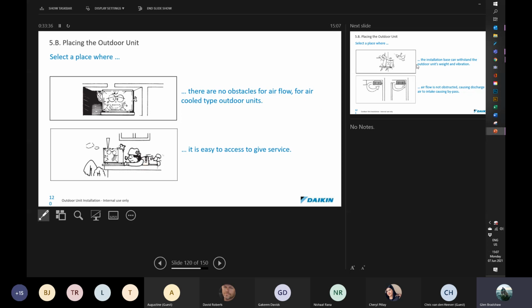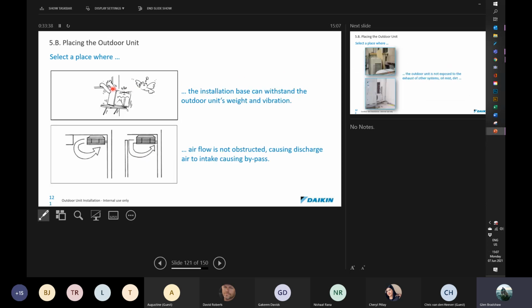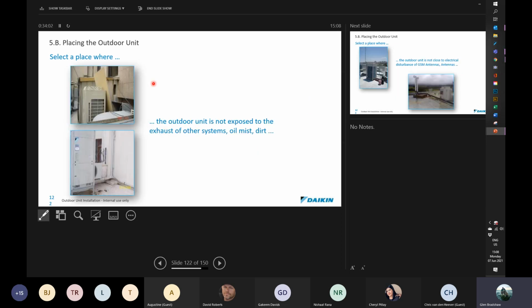Okay. Once again, the structure that it's mounted on must be able to withstand the weight and vibration of the unit. Okay, which means as well that there's no recirculation, and air is not obstructed, causing discharge air to go into the air intake, therefore causing a bypass. Okay, and over here, select a place where the outdoor unit is not exposed to the exhaust of other systems. In other words, oil, mist, dirt, things like that.